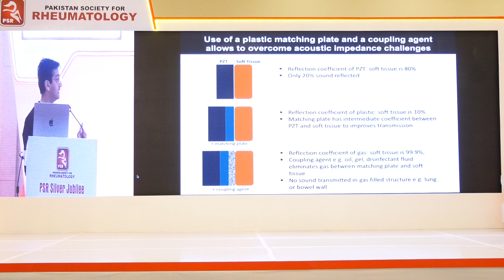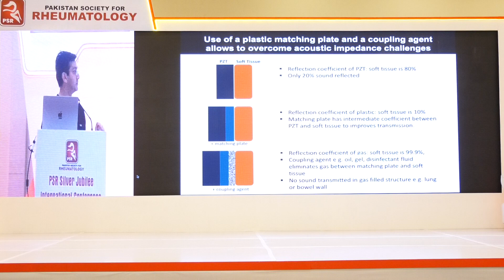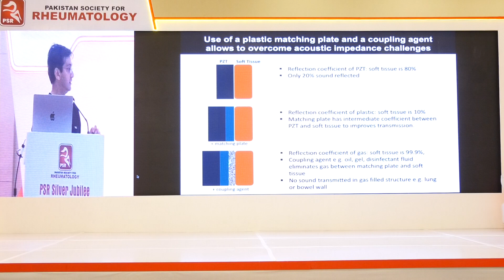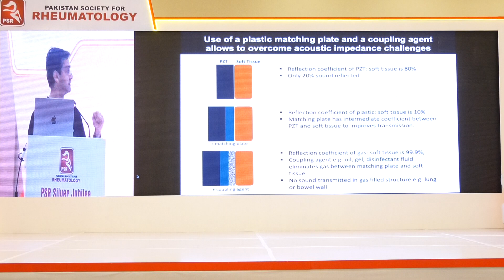Now, we can improve our sound wave transmission even more, and we have to really, because the differential between gas and soft tissue is 99%. So if you apply the disc, the plastic plate, directly onto the skin, you will have a layer of gas between the plate and the skin. And that's a problem, because the reflection coefficient there is 99.9% if you've got gas in between the skin and the plate. So what we do is we apply a coupling agent to eliminate the gas.